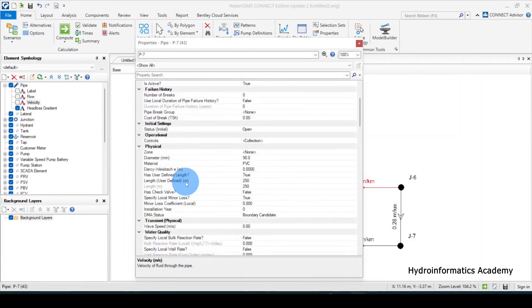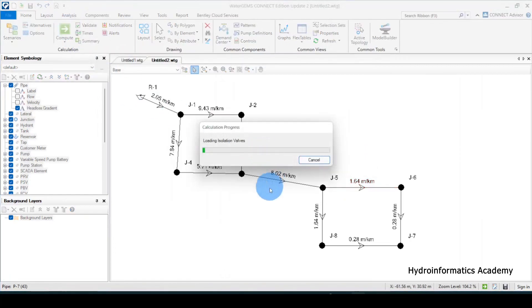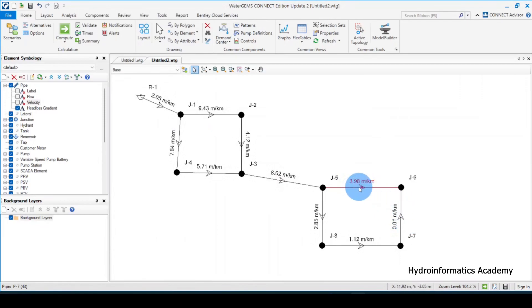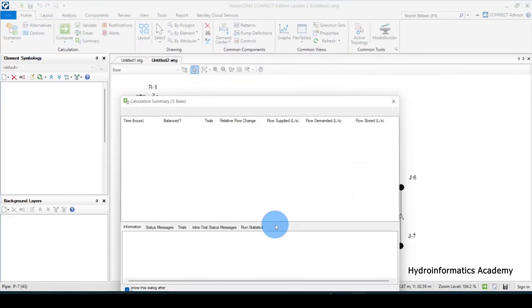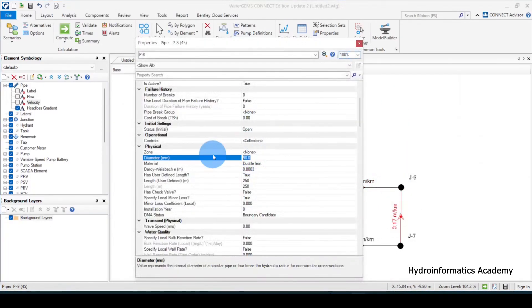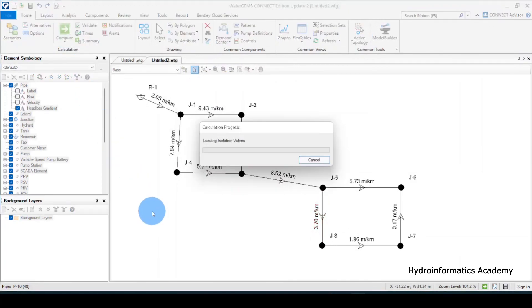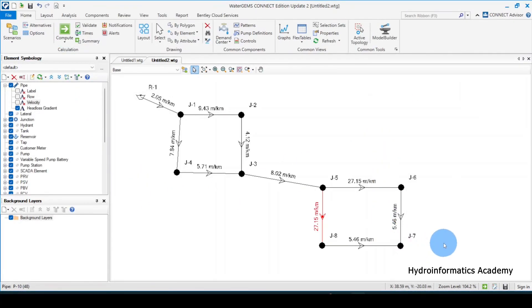I'll reduce several pipe diameters to around 63 or 50 millimeters — using the internal diameter as required. Let me click the pipe, go to pipe diameter, and change them. I'll run the model and check. After trying 50, it introduced new problems, so let me take those back up to 63 millimeters and re-run.